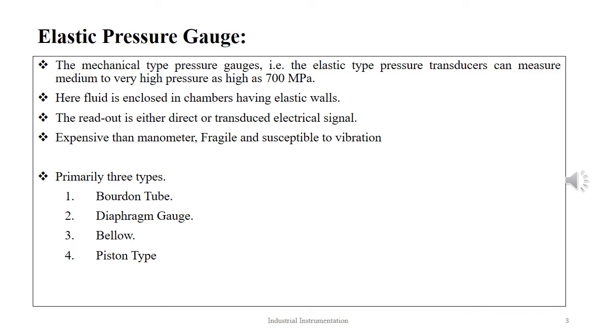The elastic type pressure transducers or gauges are used to measure medium to very high pressure, sometimes as high as 700 megapascal. In this type of gauges, the fluid is enclosed inside a closed chamber having walls made up of elastic materials. At least one side is made up of elastic element in this type of gauges. The readout from these transducers can be either a direct physical dial-based output or in form of transduced electrical signals.